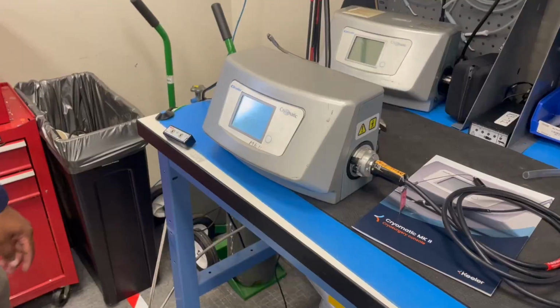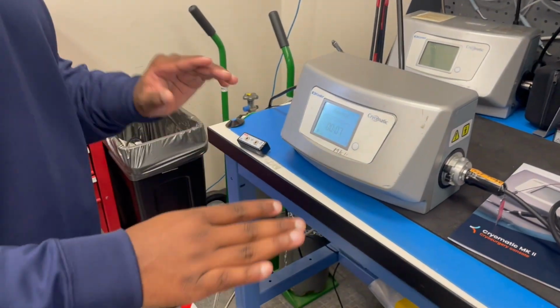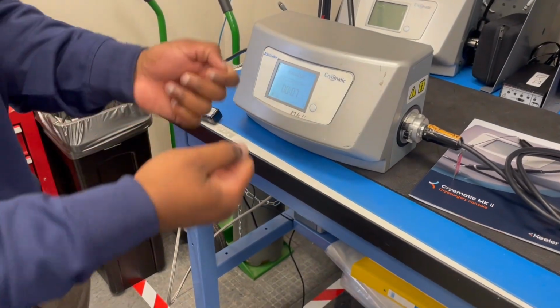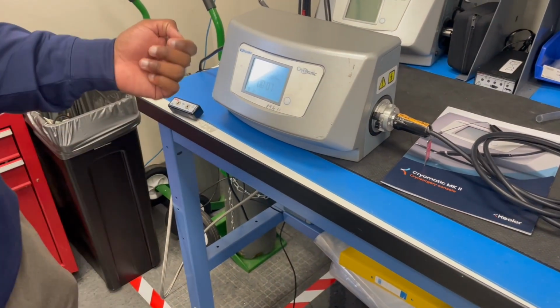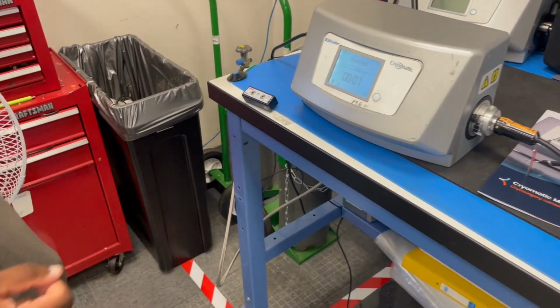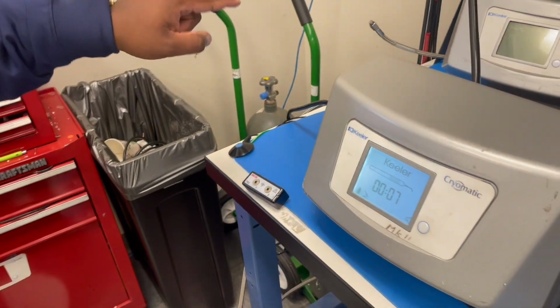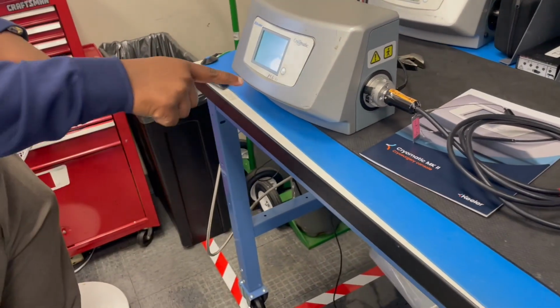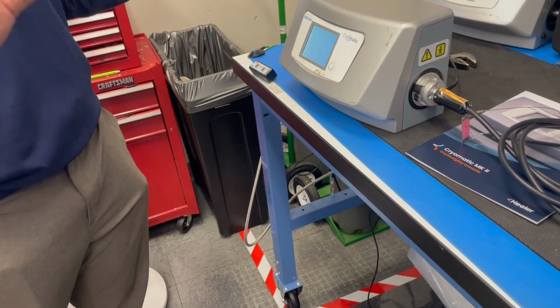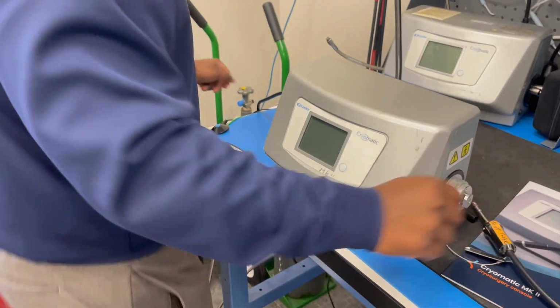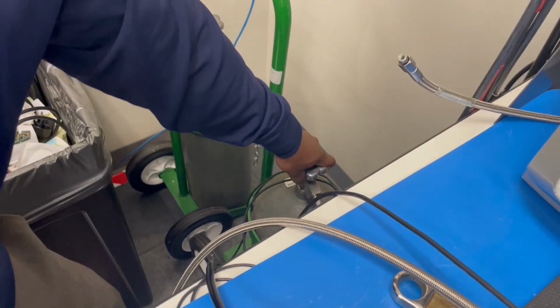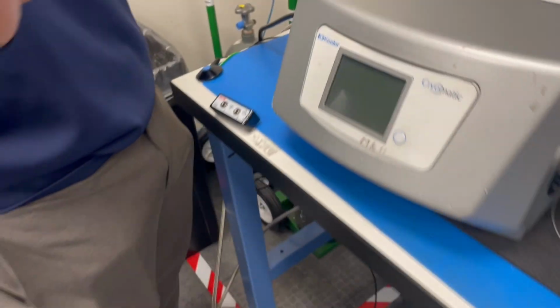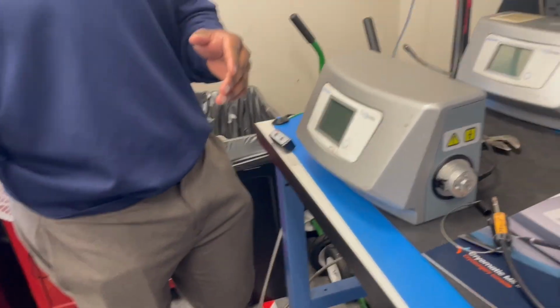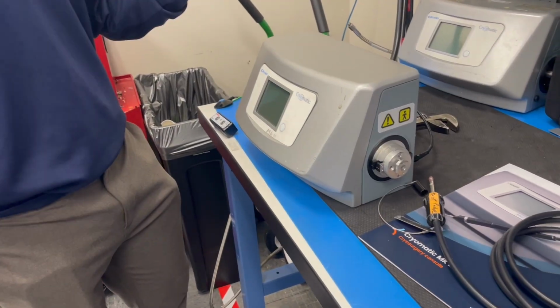But now that we have the unit set up, we're gonna do everything that we did to get the unit up and going, backwards now. So what does that look like? Just to give a quick rundown, we open the gas, we turn the machine on, we wait for it to purge, we plug the probe in, we click the play button, and we're ready to freeze. Now we're gonna remove this probe. We're going to turn the machine off. And then just tighten the gas itself, righty tighty, lefty loosey. The machine does not need to purge after, which might be common with the CE 2000. Yeah, that's huge. So literally, you're done.